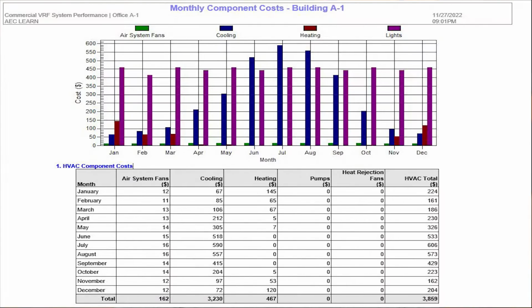Every HVAC engineer needs to know at least one load calculation software. A load calculation software helps you to calculate peak cooling and heating load of a building to size the right HVAC equipment for the building that you're designing. The most common software programs for load calculation in the US are Hourly Analysis Program or HAP and Trace3D Plus. These are both great software and they meet the requirements of ASHRAE and Department of Energy or DOE. In addition to peak load calculation, these two software can simulate building and mechanical system performance throughout the year. This type of simulation is very important for operational cost estimate and energy saving calculations.